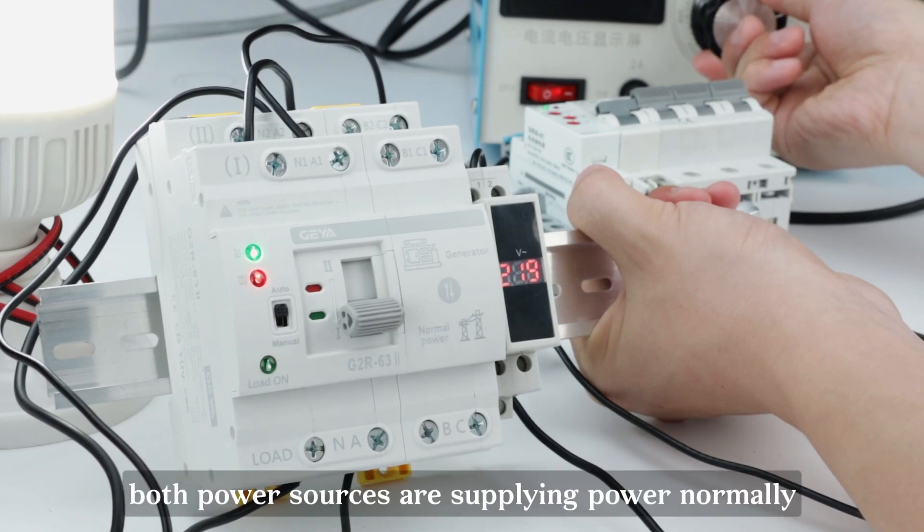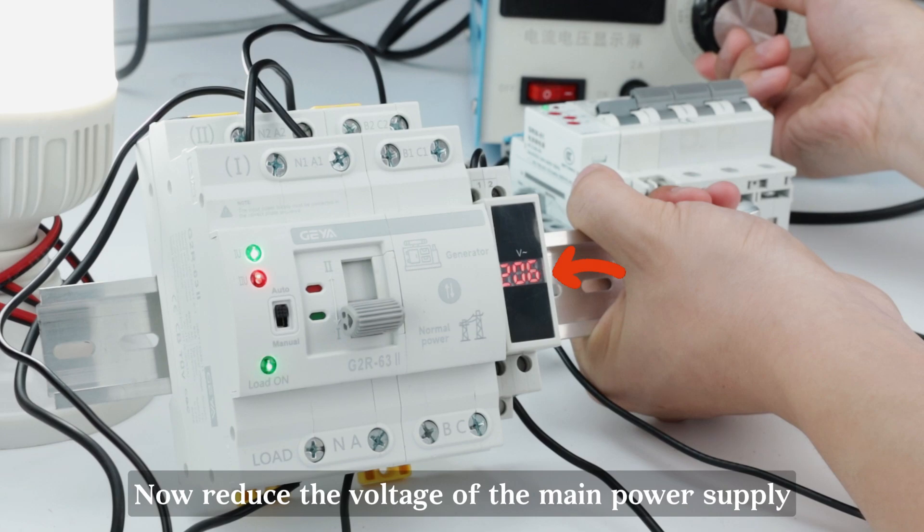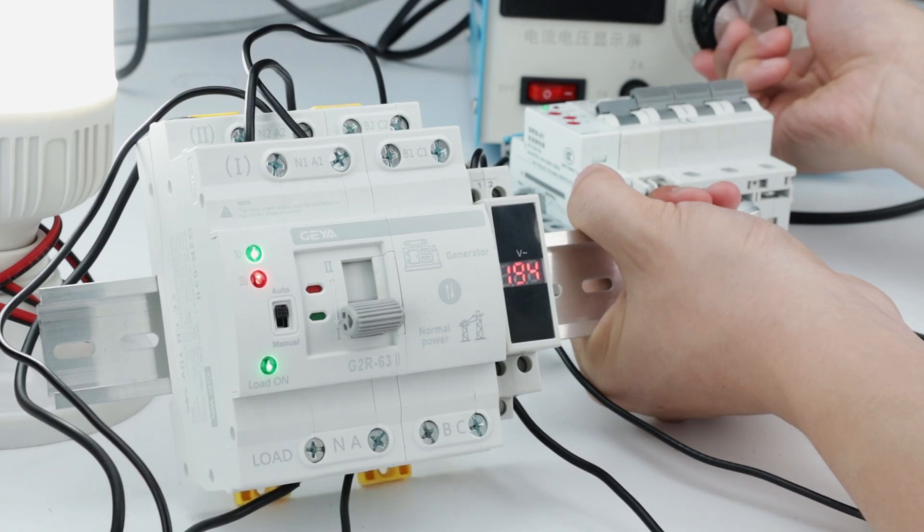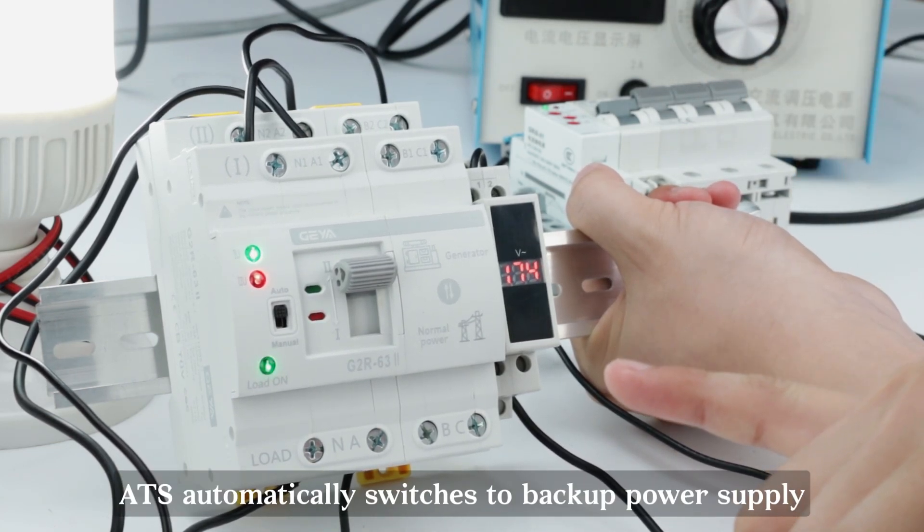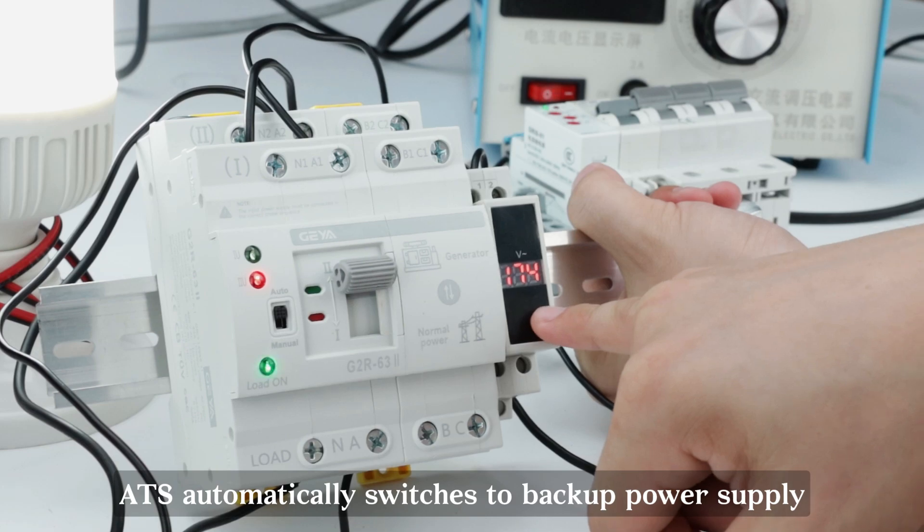At this time, both power sources are supplying power normally. Now reduce the voltage of the main power supply. When the voltage drops below 175V, ATS automatically switches to backup power supply.